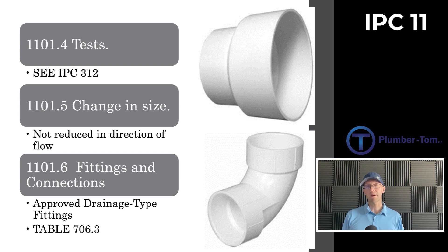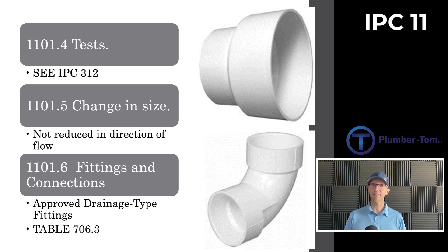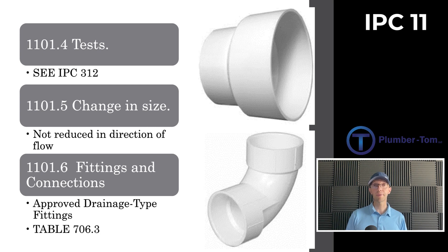1101.4 talks about tests. Just like any other drainage or water system, when we install pipes we want to make sure they're tested to hold pressure and not leak inside the building. The testing for storm drains is the same as any other drainage testing — they refer us back to Chapter 3, specifically Section 312. You have two options: water or air. Either test has to hold for at least 15 minutes. If using water, you need at least a 10-foot head of water. If using air, it's 5 psi.